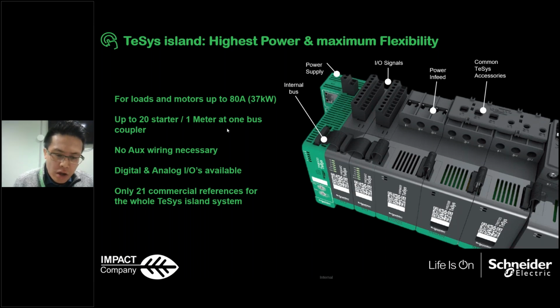And then you may ask, what if my application is more than that, more than 20 starters? No worries, because you can have a second bus coupler to communicate with another 20 starters. And then you can connect 2 islands or even 3 islands or more with the Ethernet daisy chain. So everything can be connected through the Ethernet network, and then you can access all the data for the starters.